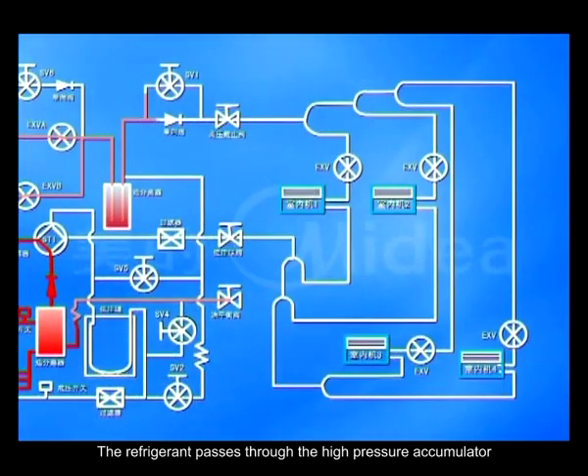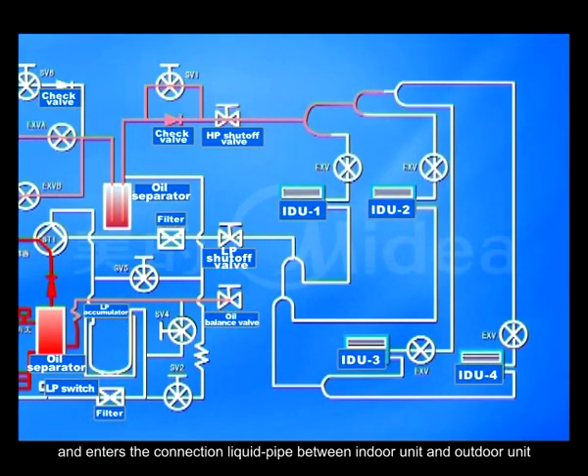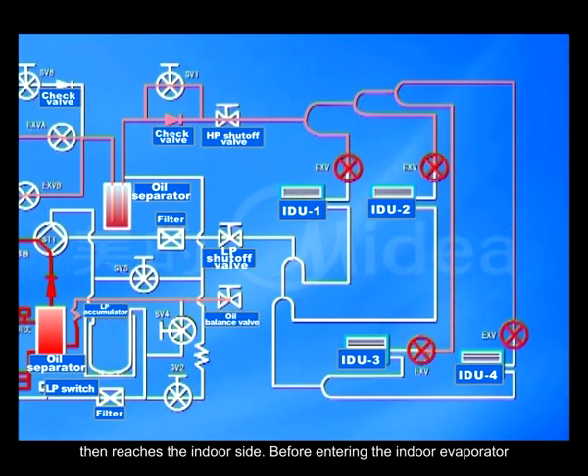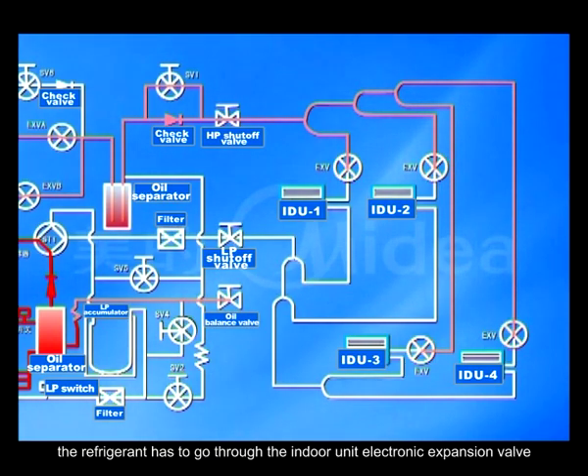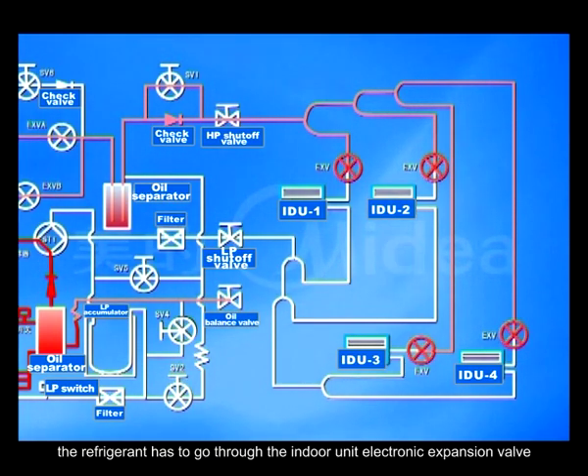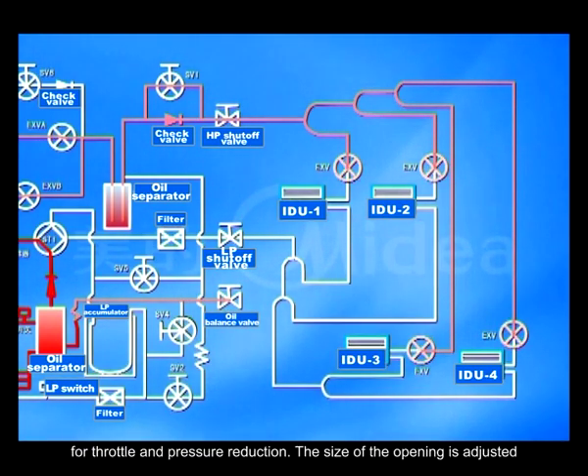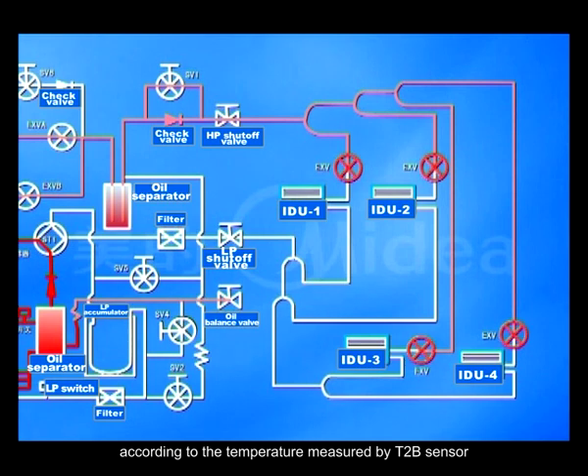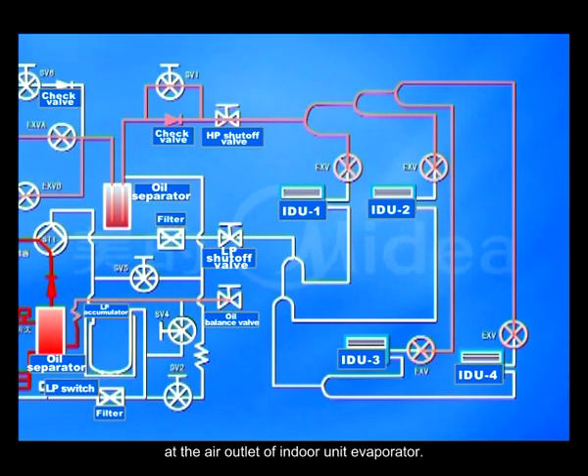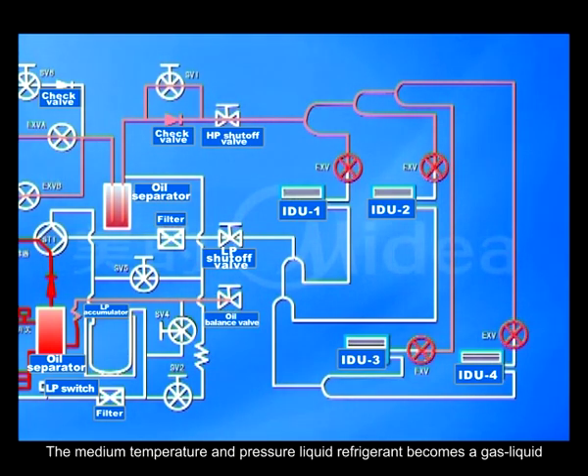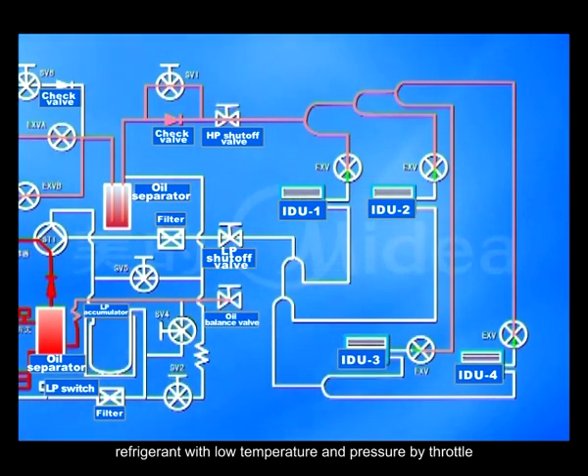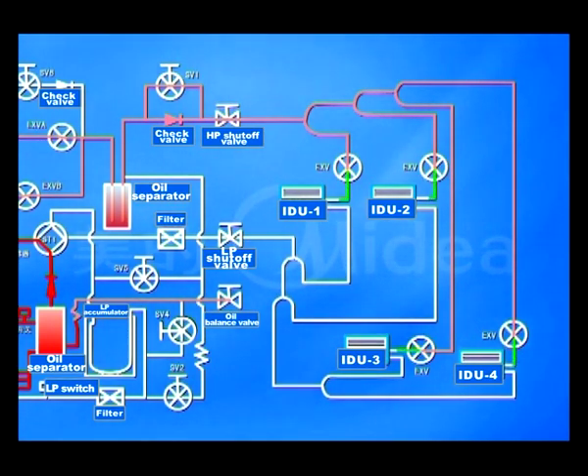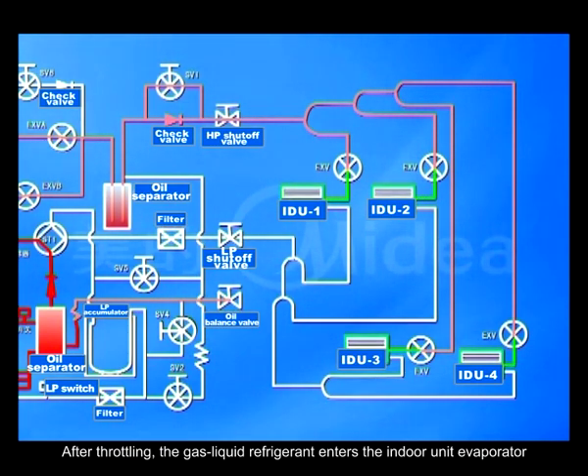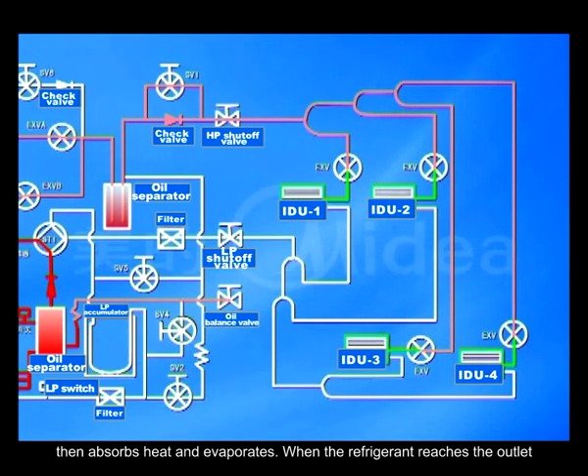The refrigerant passes through the high-pressure accumulator and enters the connection liquid pipe between indoor unit and outdoor unit, then reaches the indoor side. Before entering the indoor evaporator, the refrigerant has to go through the indoor unit electronic expansion valve for throttle and pressure reduction. The size of the opening is adjusted according to the temperature measured by T2B sensor at the air outlet of indoor unit evaporator. The medium temperature and pressure liquid refrigerant becomes a gas liquid refrigerant with low temperature and pressure by throttle. After throttling, the gas liquid refrigerant enters the indoor unit evaporator, then absorbs heat and evaporates.